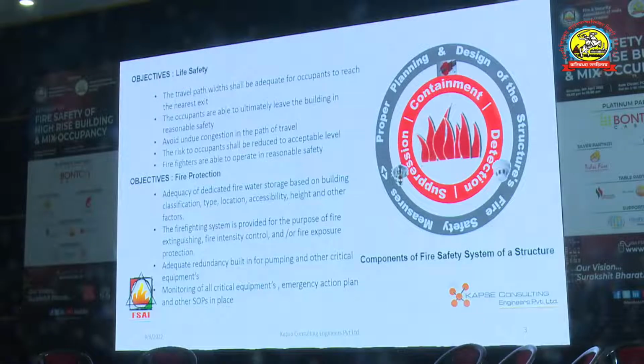Objectives: whenever you want to design something, you should know your objectives very clearly—what objective you are designing the system for. Travel path adequacy for occupants timely leaving the building, congestion due to travel, firefighters' way up with respect to carrying their hoses and their lives in terms of height—how they carry equipment up a 70-meter or 100-meter high building, it all depends. So the objective of your design has to be very clear. Suppression, detection, and containment are the three major fundamentals of fire safety design. A good suppression system without good containment won't help, and a good detection system without good suppression doesn't help either. So these three parameters—suppression, containment, and detection—are extremely important to meet the objective.